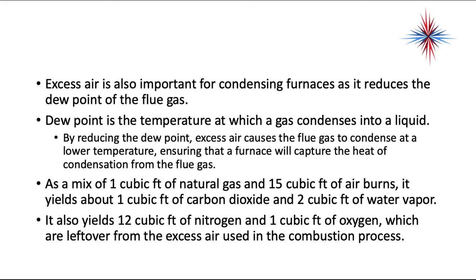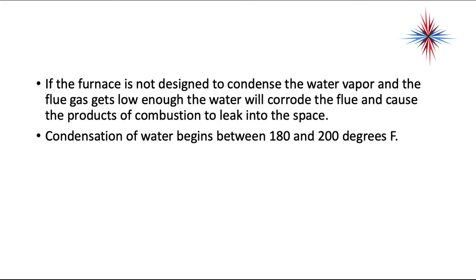By reducing the dew point, excess air causes flue gas to condensate at a lower temperature, ensuring the furnace captures the heat of condensation. Condensing furnaces capture the latent heat that occurs when a gas condenses to a liquid. When one cubic foot of natural gas and 15 cubic feet of air burns, it yields about one cubic foot of carbon dioxide, two cubic feet of water vapor, 12 cubic feet of nitrogen, and one cubic foot of oxygen as leftovers. When we burn gas it generates water vapor — condensing furnaces condense that water vapor, and the water runs off into a condensate drain. If a furnace is not designed to condensate the water vapor, flue gas cooling too low will cause water to corrode the flue and let combustion gases leak into the living space.